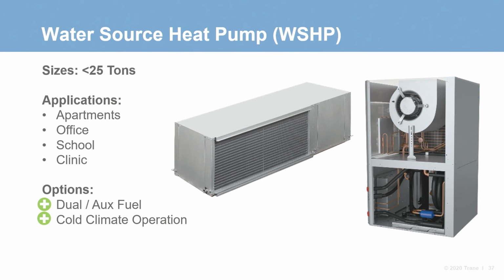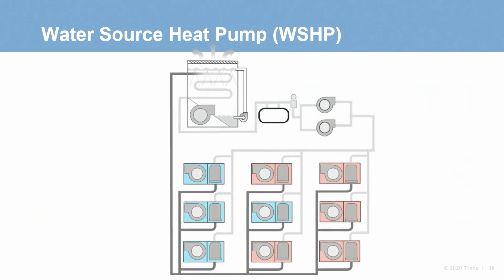On top of that, the condenser loop can be tempered with either electric heat, heat pump heat, or gas-fired heat. This flexibility allows the system to operate in cold climates without issue. In terms of electrification, water source heat pumps have a lot to offer. Since all the heat pumps share a common condenser loop, heat recovery is maximized in the system. Any water source heat pump can provide heat recovery to any other water source heat pump on the system.